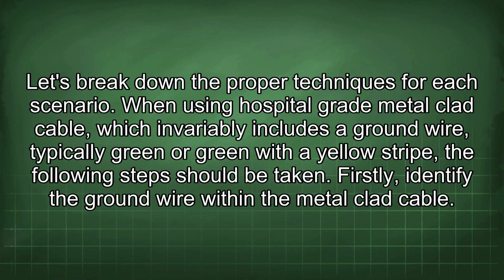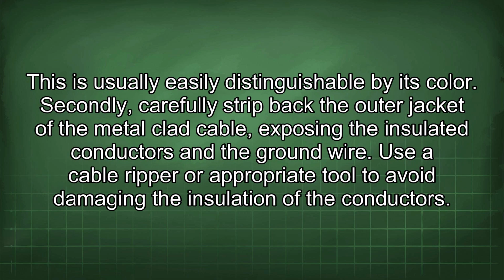When using hospital-grade metal-clad cable, which invariably includes a ground wire, typically green or green with a yellow stripe, the following steps should be taken. Firstly, identify the ground wire within the metal-clad cable. This is usually easily distinguishable by its color. Secondly, carefully strip back the outer jacket of the metal-clad cable, exposing the insulated conductors and the ground wire. Use a cable ripper or appropriate tool to avoid damaging the insulation of the conductors.